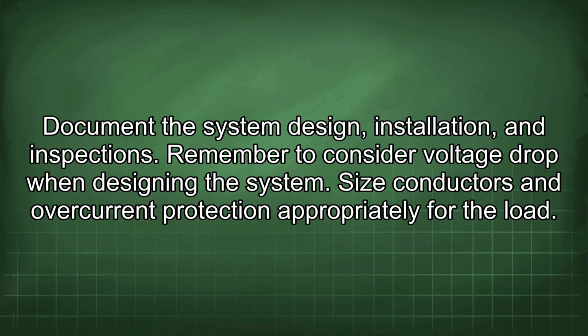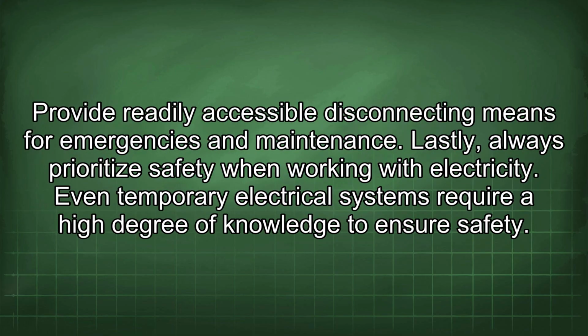Remember to consider voltage drop when designing the system. Size conductors and overcurrent protection appropriately for the load. Provide readily accessible disconnecting means for emergencies and maintenance. Lastly, always prioritize safety when working with electricity. Even temporary electrical systems require a high degree of knowledge to ensure safety.